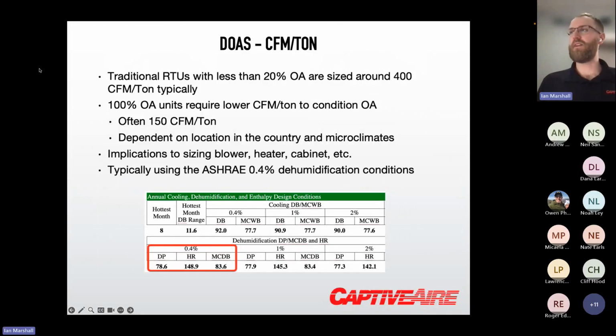I hit on this because DOAS is typically sized quite a bit differently than a traditional rooftop unit, or RTU. A traditional RTU, I think we say 20% outside air is the max they can handle, based off of their coil designs. A DOAS unit, and our unit, can handle up to 100% outside air. Traditional RTUs are typically running around 400 CFM per ton, where that is not necessarily the case for a DOAS.